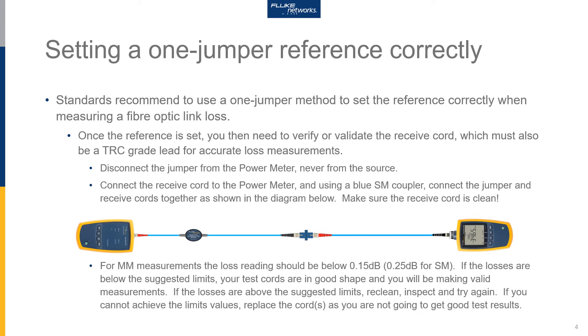If the measured losses are above the suggested limits, reclean the field connectors, inspect to confirm they are clean, and give it a try again. If you cannot achieve the suggested loss values for the mated cords, you really need to consider replacing the cords because they may be worn out. If you can't get low mated results when verifying the cords, you are not going to get good test results. If your reference is poor and your cords are poor, you are going to get poor measurement results.